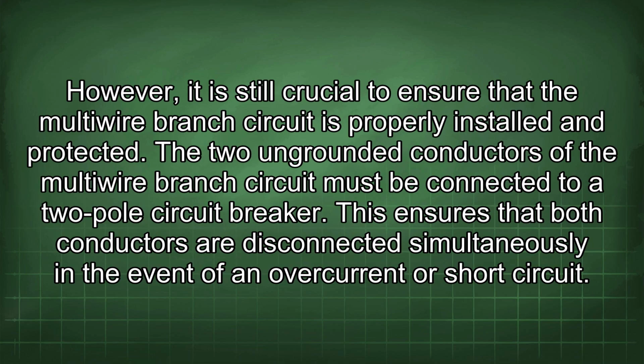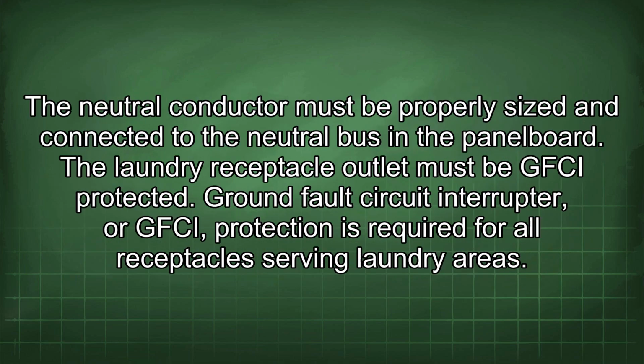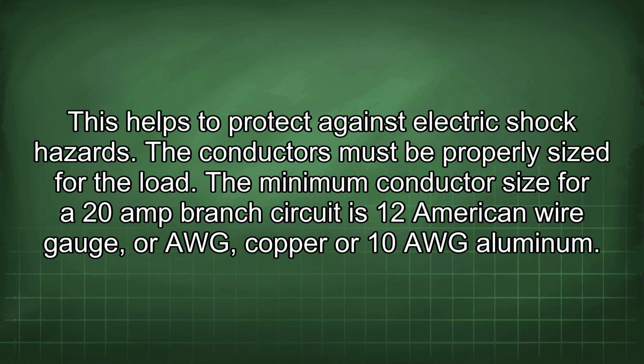However, it is still crucial to ensure that the multiwire branch circuit is properly installed and protected. The two ungrounded conductors of the multiwire branch circuit must be connected to a 2-pole circuit breaker. This ensures that both conductors are disconnected simultaneously in the event of an overcurrent or short circuit. The neutral conductor must be properly sized and connected to the neutral bus in the panel board. The laundry receptacle outlet must be GFCI protected. Ground fault circuit interrupter, or GFCI, protection is required for all receptacles serving laundry areas. This helps to protect against electric shock hazards.